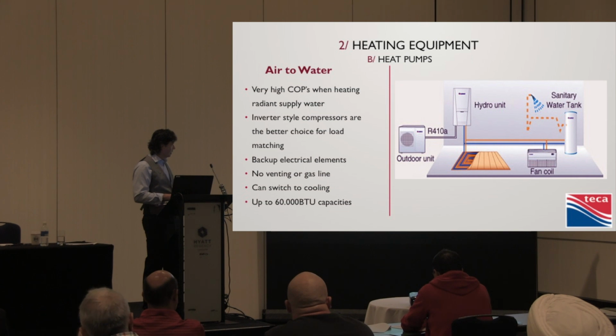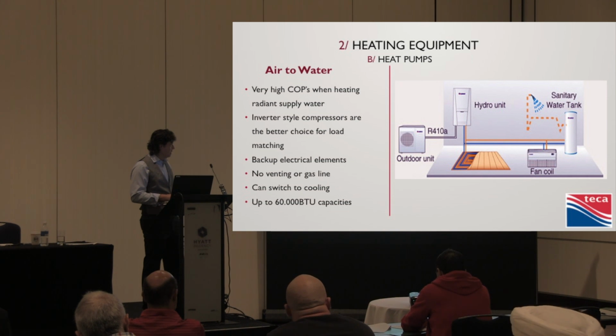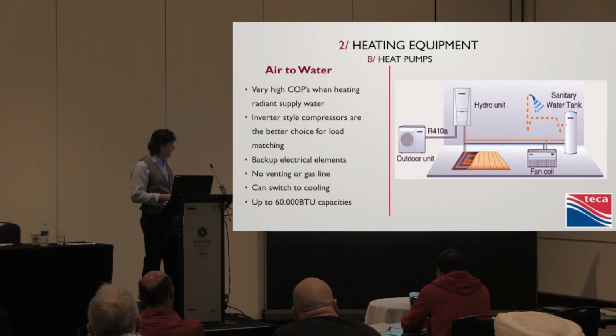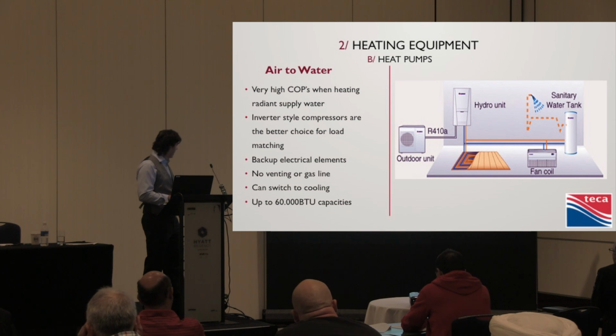They're used a lot in Europe right now and Asia. These guys have it tied onto a storage type tank. It comes with a built-in control with a sensor that says, okay, this is calling now, so let's switch our three-way valve and go off and heat this until it's warm, and then we can go back and do radiant floor or our fan coil or whatever else we want to heat or cool with water. Very high COPs in radiant water heating.